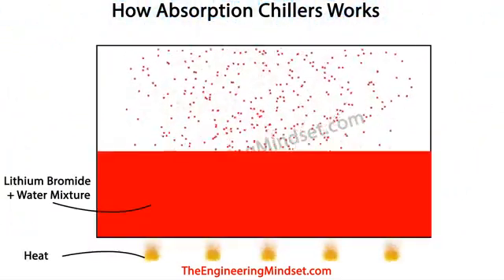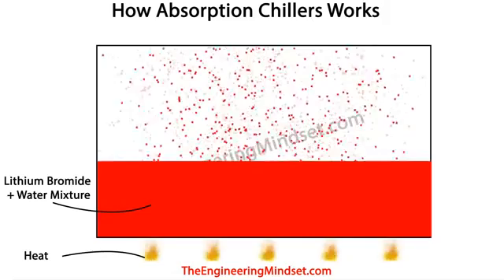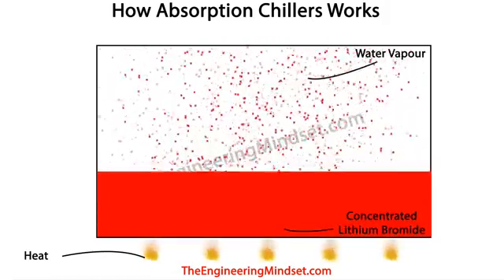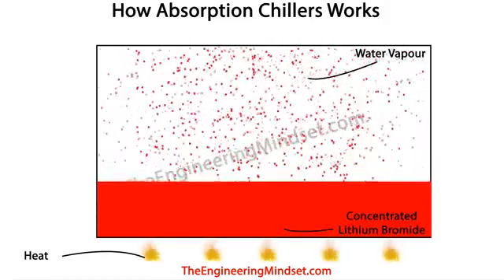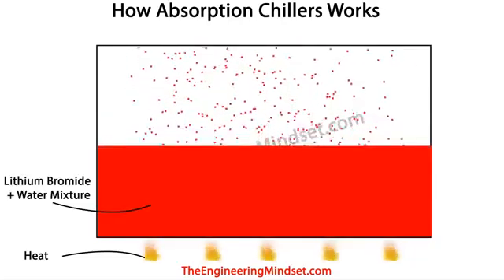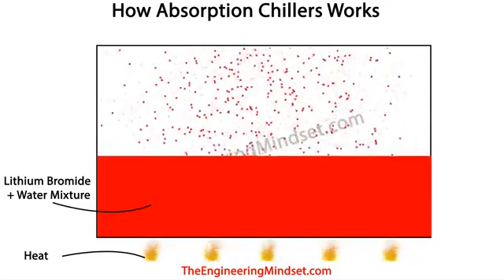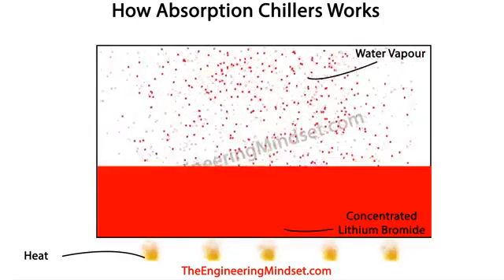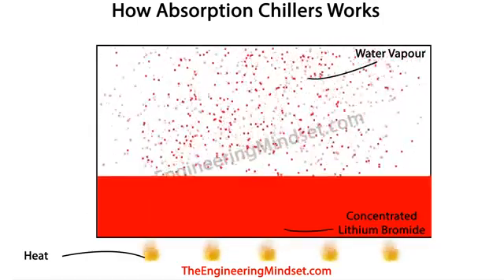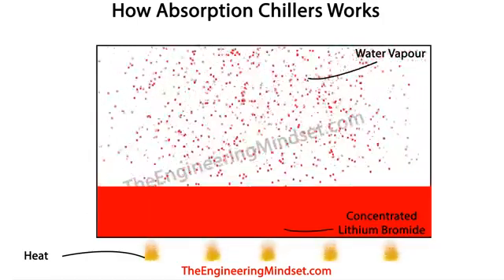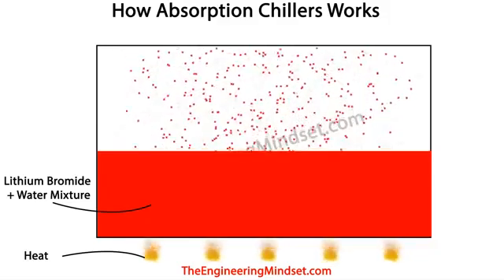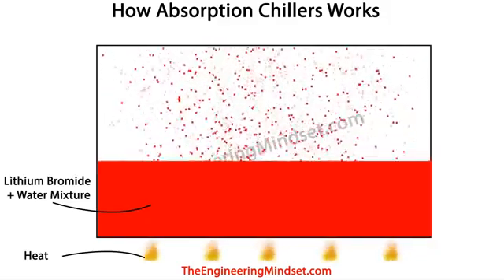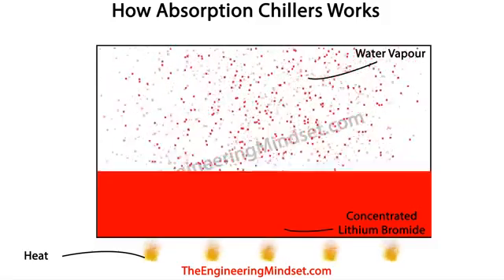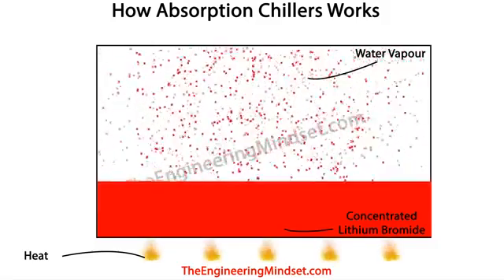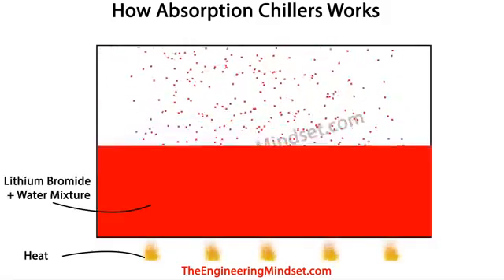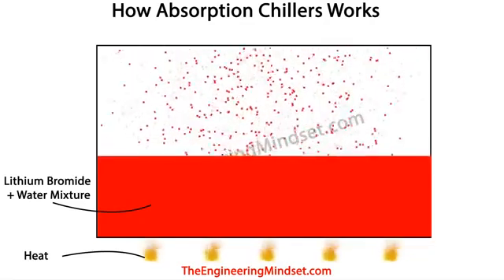The third point to remember is that when water and lithium bromide are mixed together, you can separate them again just by adding heat. So as you apply heat to this, the two will separate, where the lithium bromide particles will become heavier, and so they will condense and come towards the bottom of the tank or the reservoir, and all the water vapor will boil off and head upwards to become steam or water vapor. So you can separate the two just by applying some heat.